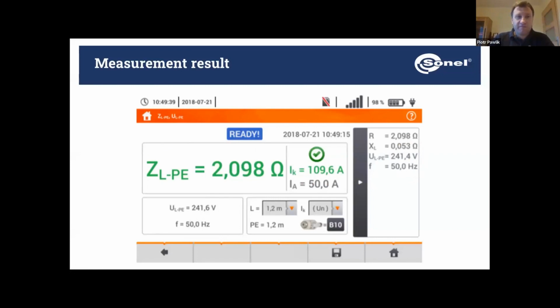Now, in case of our higher models of the meters, like here the MPI 540, we have a database of the breakers. So in this particular situation, the breaker used was a B10. So we enter it over here from our database, and the meter knows that the current triggering B10, that's 50 amps. Further on, the meter will calculate for us our fault current. So here we can select what calculation method we are using, either nominal voltage or the actual measured voltage. Here, the actual voltage is 241 volts. So we use UN, the nominal voltage of 230 volts. And 230 volts over 2.098 ohms, that's 109.6 amps. So this is the fault current flowing in our circuit.